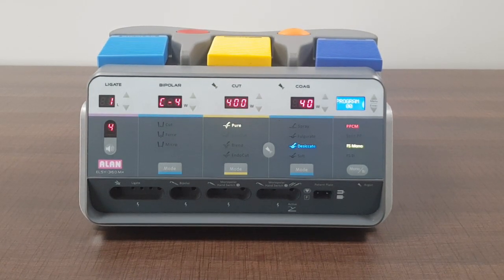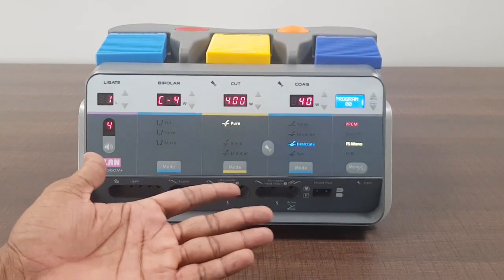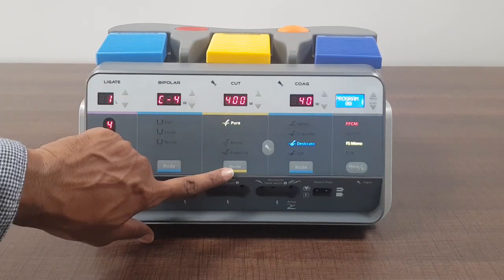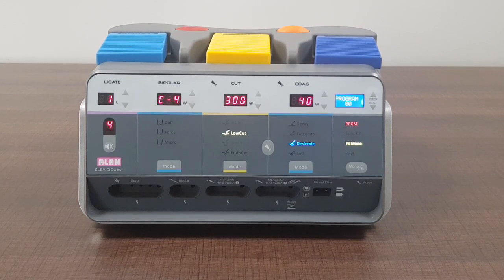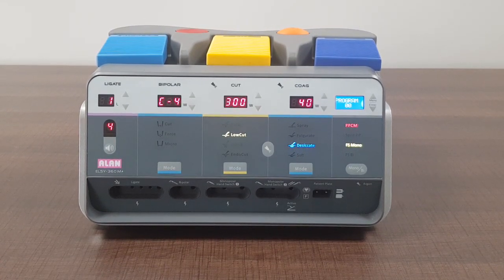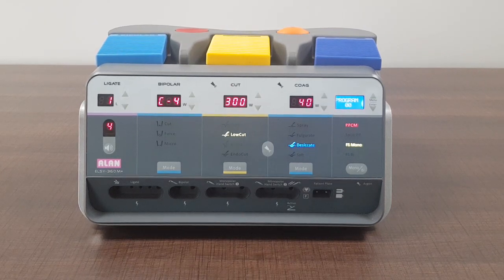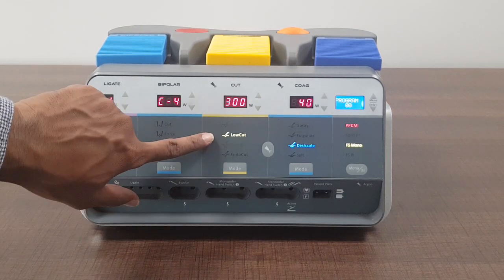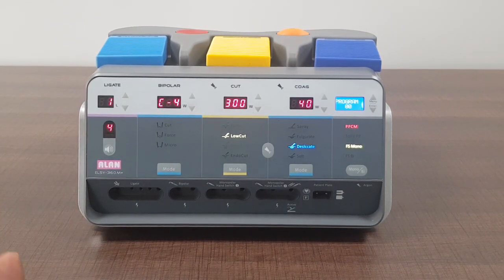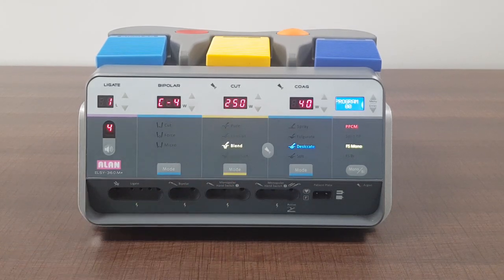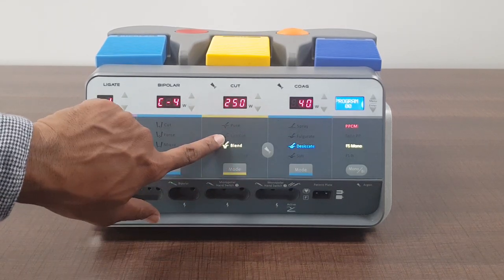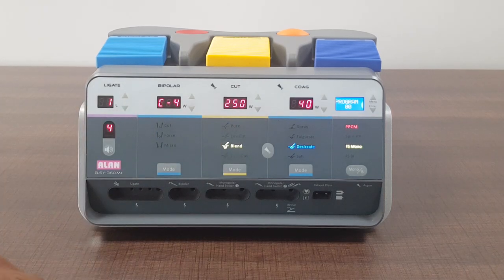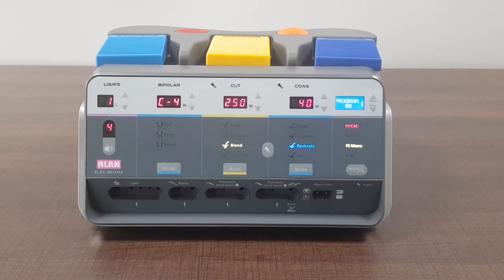Here you can keep at a wattage of around 25 and 30 depending upon which organ you're using it and basic monopolar pencil either with hand switch or a foot switch you can use this. Second is low cut. This is a special mode built for laparoscopy. When you use this, the smoke is reduced to a great extent because when you do laparoscopy there is camera and other things and the possibility of gas generation is quite high. So this special mode is for laparoscopy. You can also use it in open for cutting. The maximum wattage in low cut is 300 watts and the maximum wattage in blend is 250 watts.